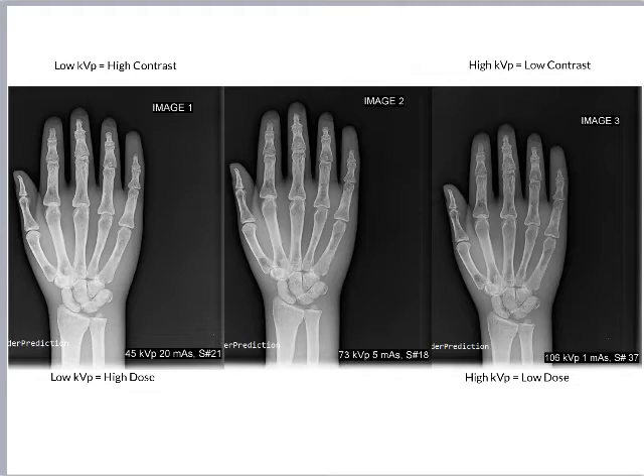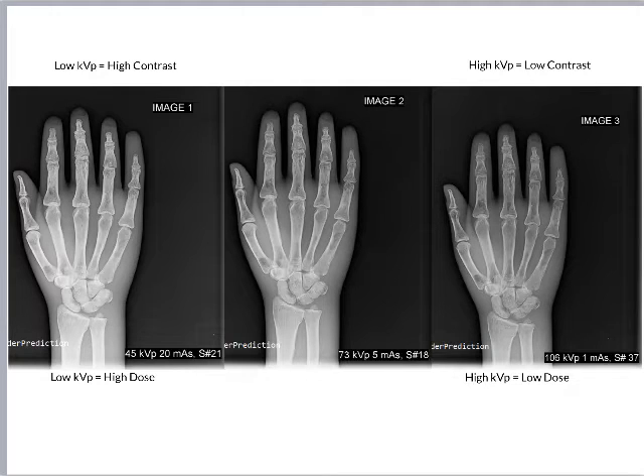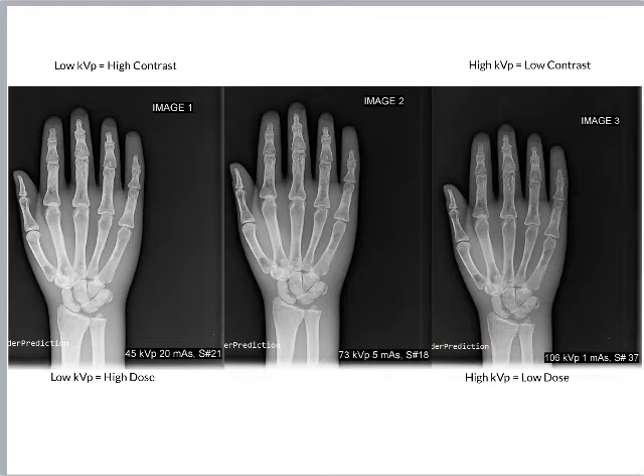Conversely, a high KVP equals a low subject contrast. We've done an experiment here — unfortunately the effects of these settings don't fully translate once I've captured the DICOM images and converted them to JPEG for PowerPoint. These are three different images taken at three different KVP settings. The mAs was varied approximately along the lines of the 15% rule, so as we increased KVP we decreased mAs. This was done on a Fuji system, and the S number, which records image receptor exposure, doesn't vary all that much.